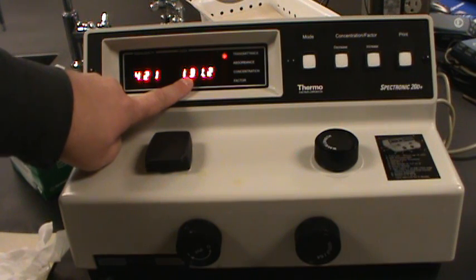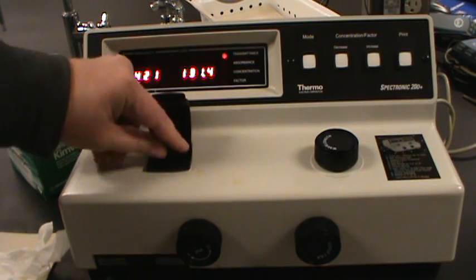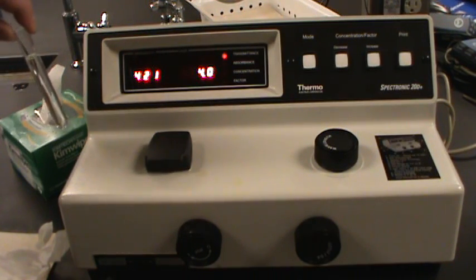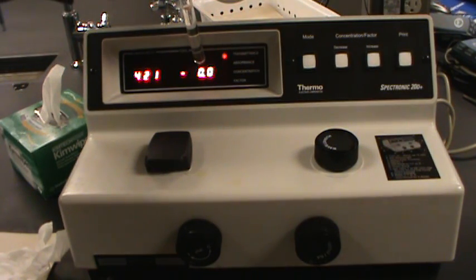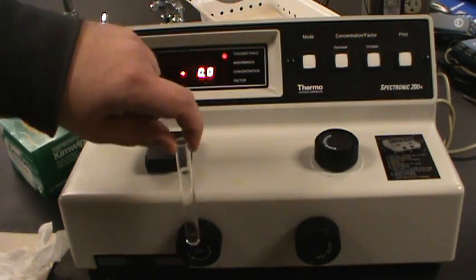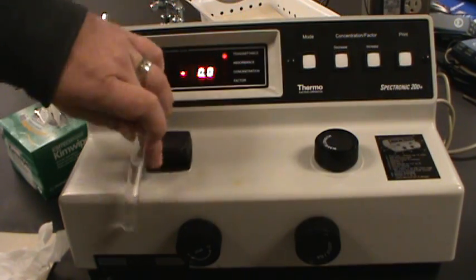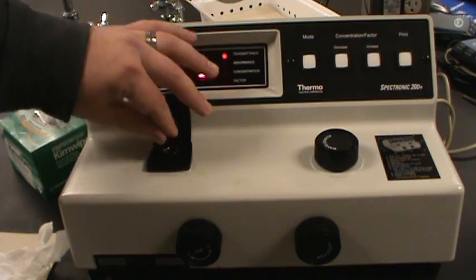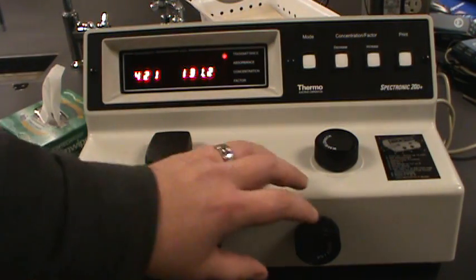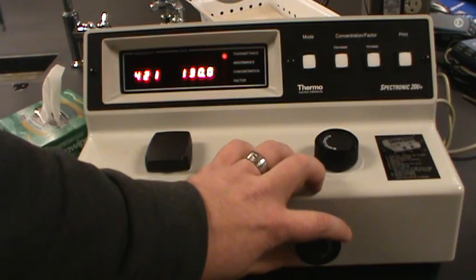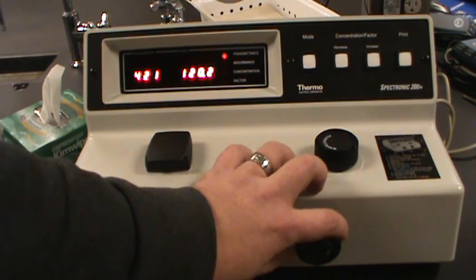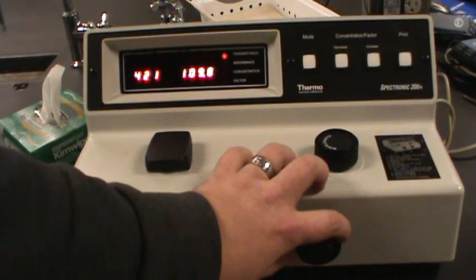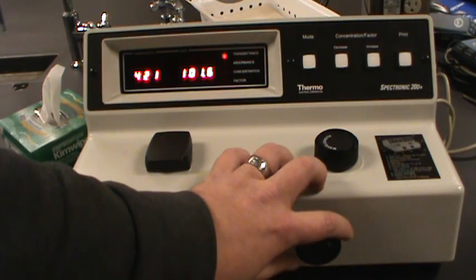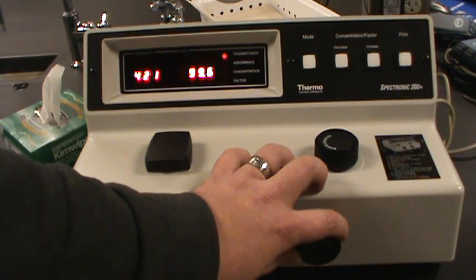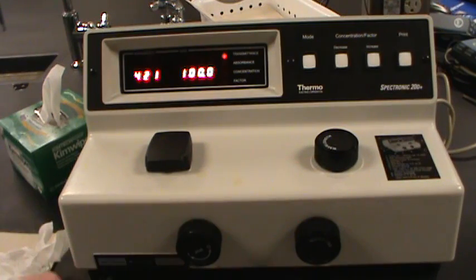Notice we're at more than 100%. If I take this out, it should still be at 0. So you can always check your 0% calibration, but this one's still good. It should stay good. Let's put in our sample and adjust the 100% calibration down to 100%. That looks good.